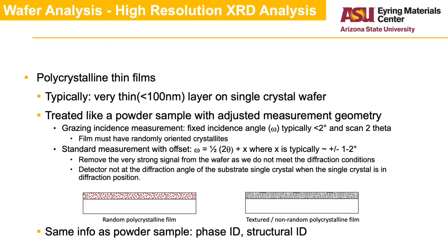For thicker thin films and films with texture, one would typically do a measurement similar to the one done on a powder, where the incidence angle varies as a function of detector angle. However, to avoid measuring the signal from the substrate, an offset is added, so the incidence angle is not half of the diffraction angle, which would typically bring the substrate into diffraction condition when the detector is at the angle where the wafer diffracts, producing a very strong peak and often some artifacts.